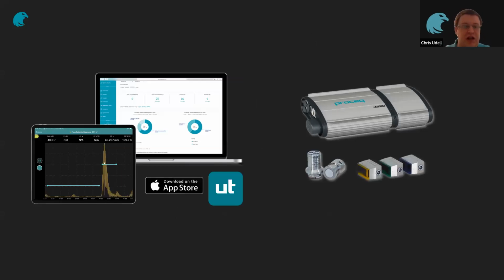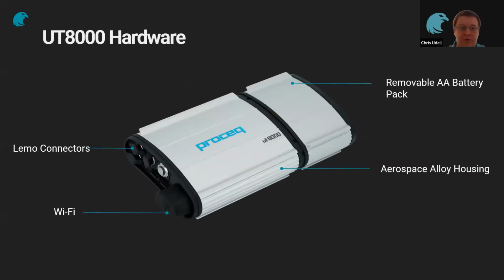So now we can introduce our response to this, the conventional ultrasonic Proceq UT8000. It's a future-proof digital flaw detector for the next generation of flaw detectors. We start by looking at the hardware. We have a lightweight aerospace alloy, which is also IP67 and drop proof, but we've still managed to keep the weight of the combined battery and the flaw detector at around 600 grams. We've got LEMO connectors, so you can connect any probe that you currently have. And we have USB-C ports in there as well, so you can connect other devices.